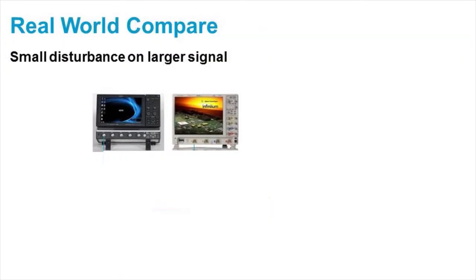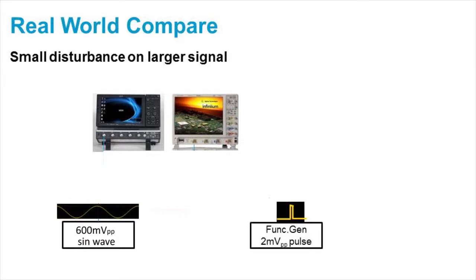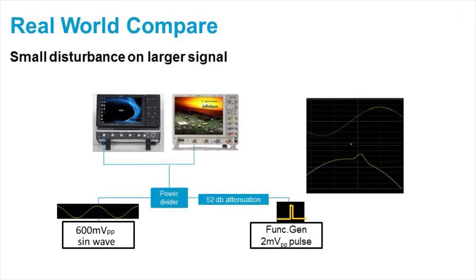So let's look at a real-world comparison. I have a setup where I've input a 600 millivolt peak-to-peak sine wave from an Agilent MXG that has very low noise on it. And superimposed on that waveform, I have a very tiny 2 millivolt pulse that happens each time at the peak of the sine wave. Let's see what it looks like on both the LeCroy 12-bit scope and the Agilent 9000 series scope in 12-bit mode.